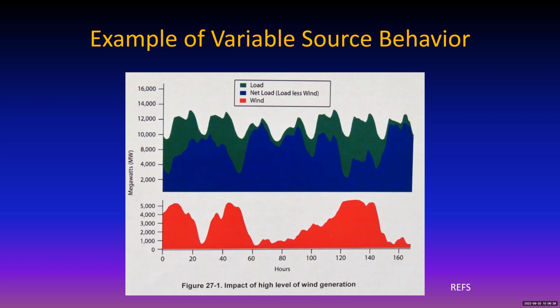But when you add the red, the blue only provides the amount shown in the picture, and that all looks well and good, except there's one interesting challenge. If you look at the slope of the blue line and the slope of the green line around 55 hours, you notice the slope of the blue is much steeper than the slope of the green. The reason is because all of a sudden the wind is going away, so the conventional generation has to make up for the loss of wind power faster than it would have had to simply follow the load. And that's a challenge.